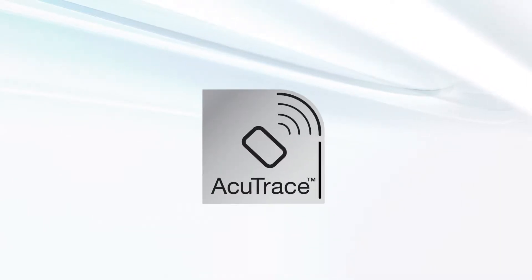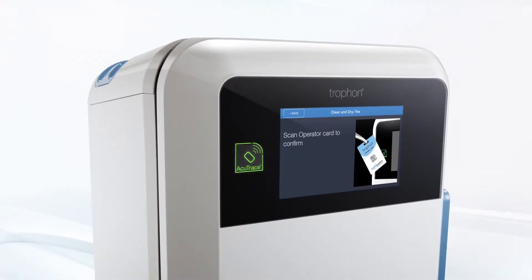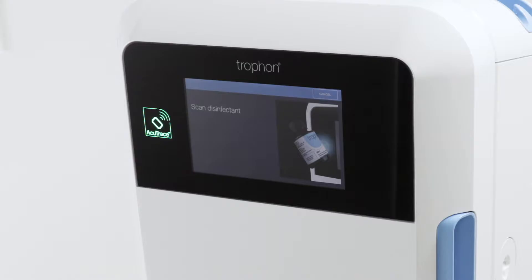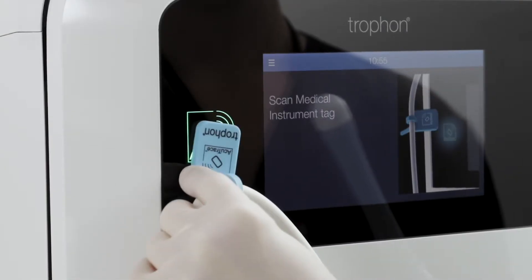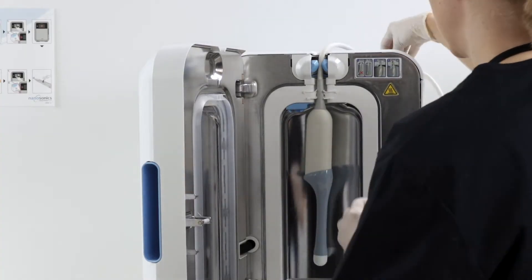AcuTrace is an automated HLD traceability system that uses RFID — Radio Frequency Identification Technology. trophon2's AcuTrace-enabled accessories and consumables contain RFID chips that store digital information. As you step through the ultrasound probe reprocessing workflow, the built-in AcuTrace reader captures and stores the digital data.